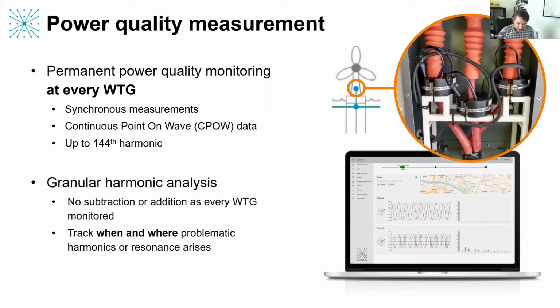Another key factor here is that we provide granular analysis of harmonics. We're not just looking at one location in the wind farm and trying to make our best guess of what's going on. We can readily deploy this at multiple locations around the wind farm at key locations. That could be at the start of the string and at the end of the string, or it could be at every individual turbine for maximum visibility. It means we see everything. We see every single contribution to our harmonics.